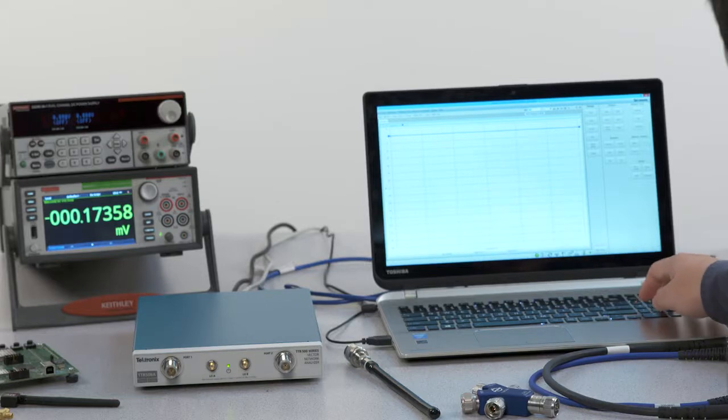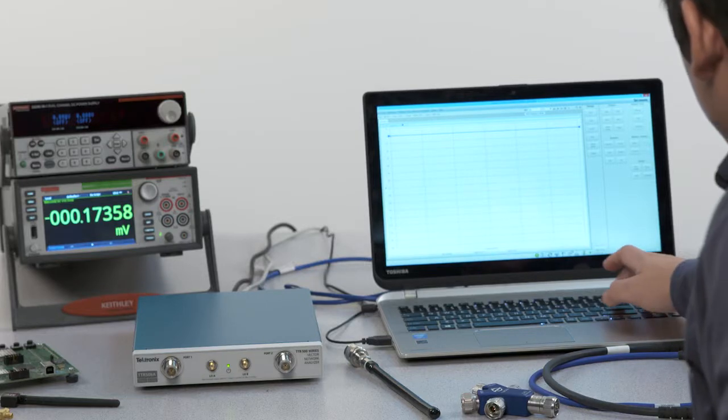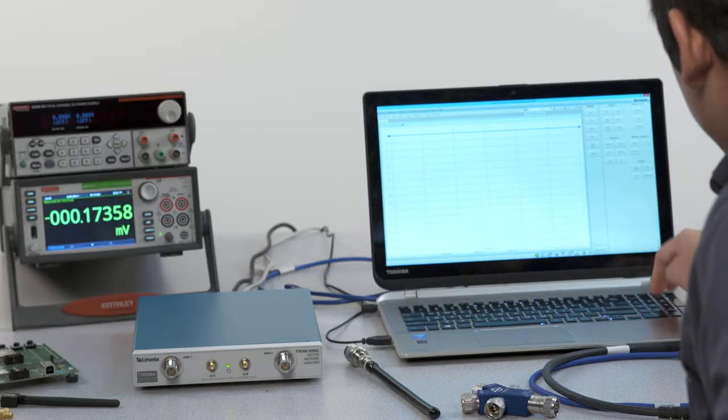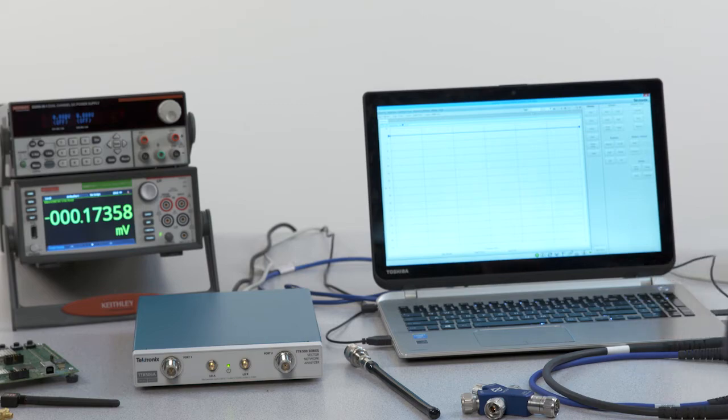Do that by first selecting the start frequency under the stimulus, and you can see that when I click that, this top menu here allows us to input a start frequency and we're going to select 100 megahertz just for this example.